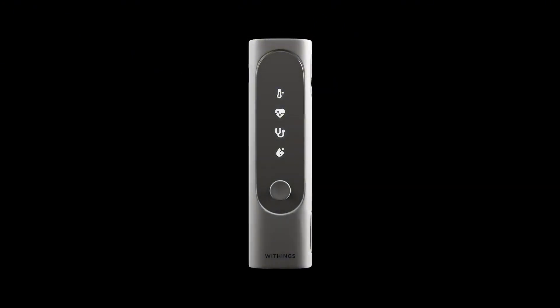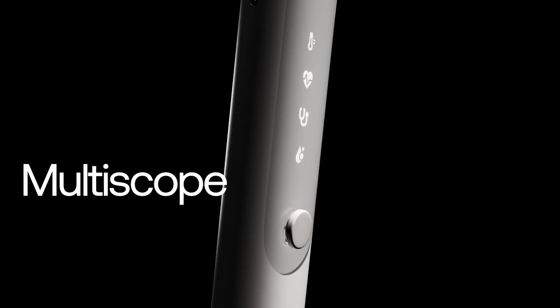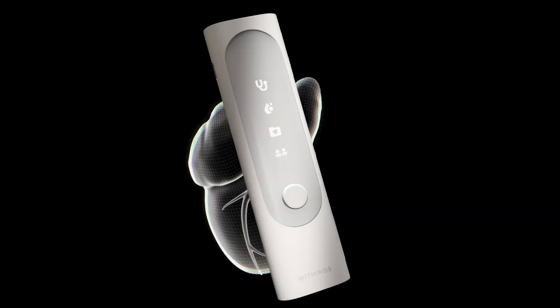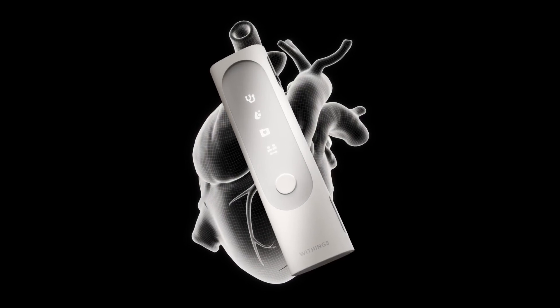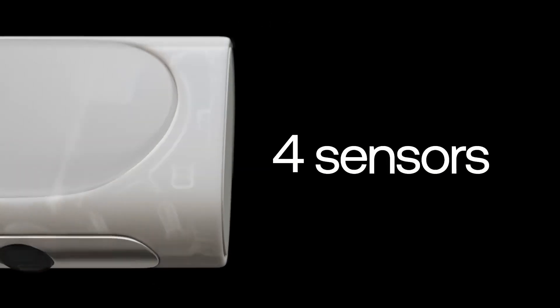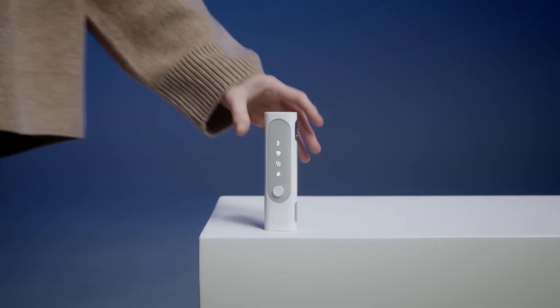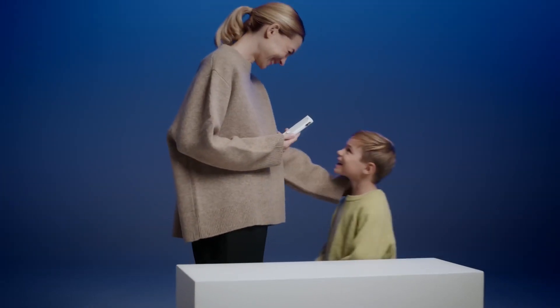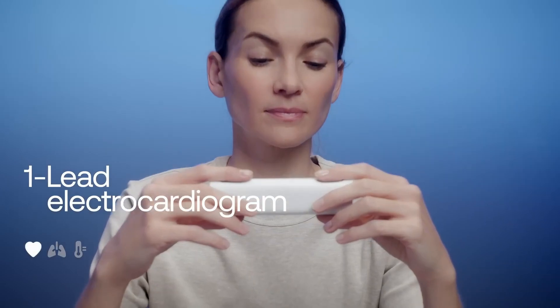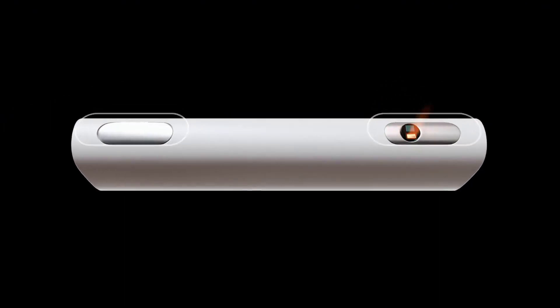At the center of the device, a large black plastic area houses a 4.8 centimeters diagonal LCD screen. Although not touch sensitive, this screen provides a clear interface for navigating between the different features. The device is also equipped with a directional button that makes navigation easy depending on the horizontal or vertical orientation of the BeamO. The finishes are neat with integrated metal triggers for the electrodes and a USB-C port for charging and connecting headphones.